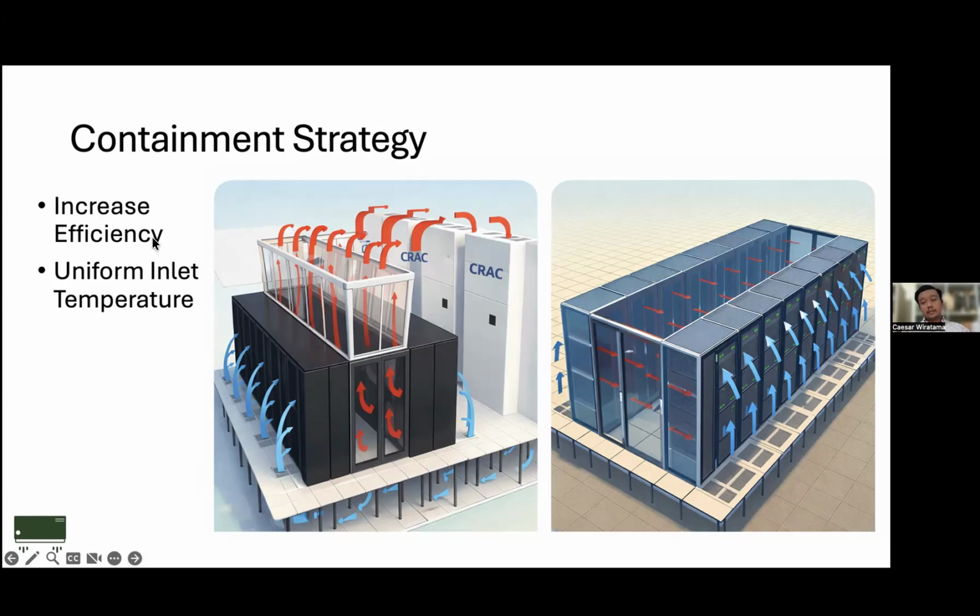It will increase the efficiency of the cooling and also give a uniform inlet temperature because we eliminate the recirculating problem. But it will increase your budget. It will add to your cost of materials and also work. And yeah, again, that is engineering. We have to deal with some trade-off between the cost and efficiency of performance.